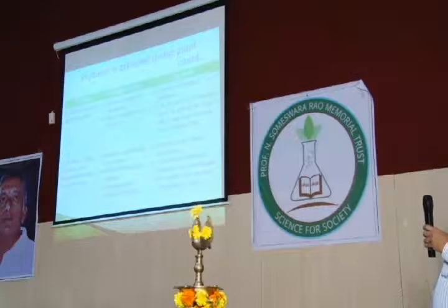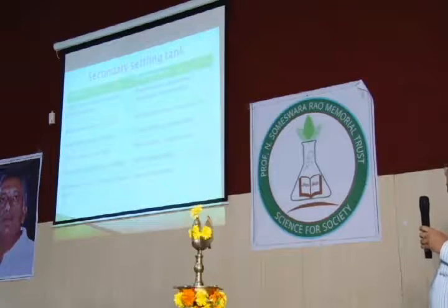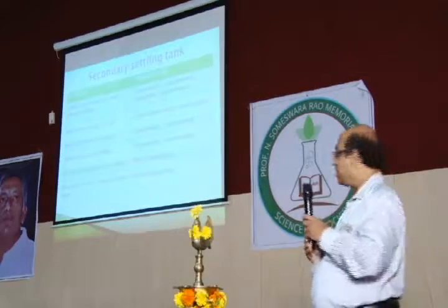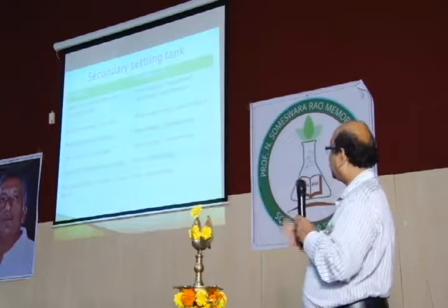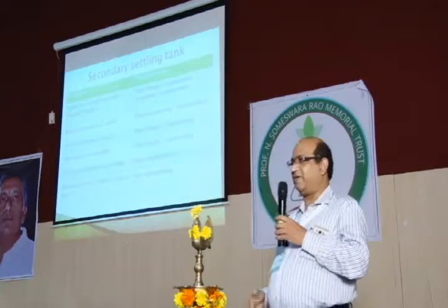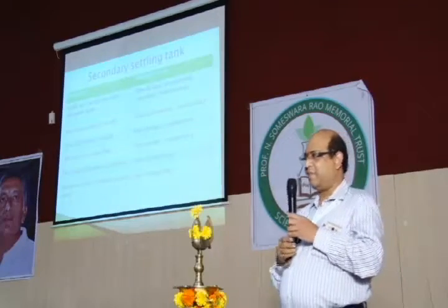Sometimes there are dead spots, sometimes returns having low suspended solids and other things. These are some of the points. Second settling tanks also, immediately issues will come there too. What happens? Many times solids are carried out. Even excellent EPC persons sometimes have improper design.